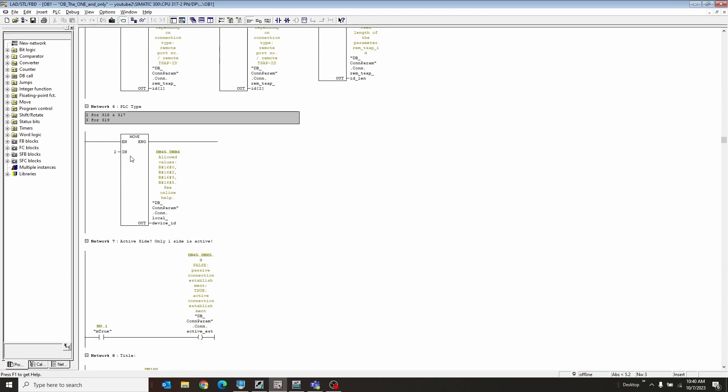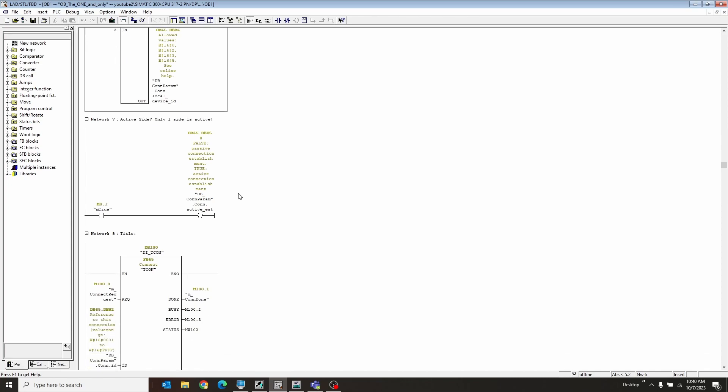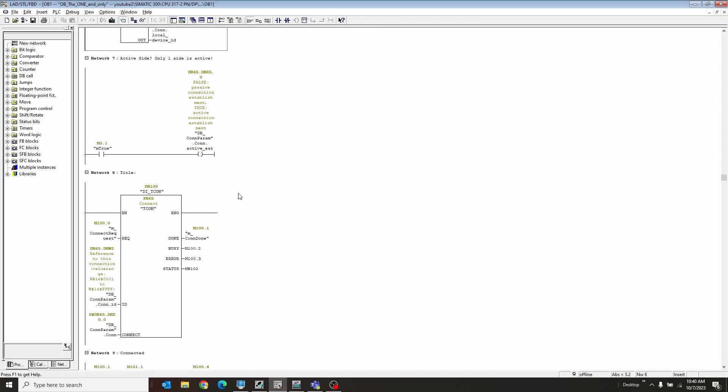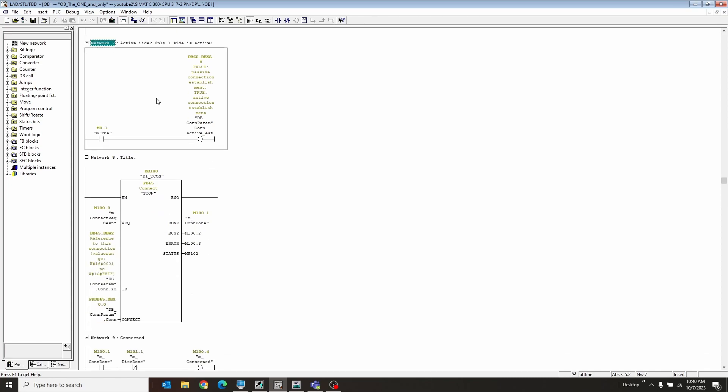PLC type is important. If you're working with a 315 or a 317, you choose a 2 for this. If you're working with a 319, it's a 3. In my case, both of my PLCs are 2s. Moving on, there's only one active side to the connection. Is this side the active side? So in this case, I put true for this one.